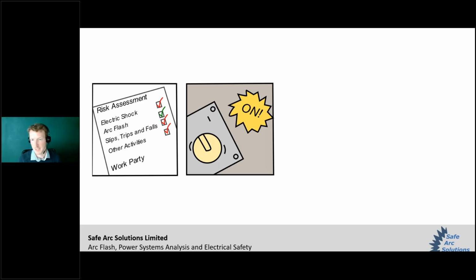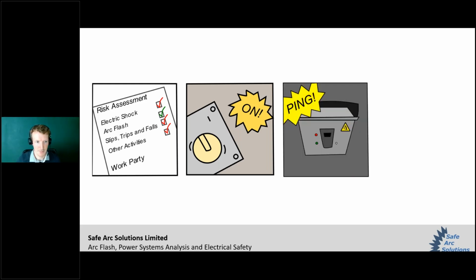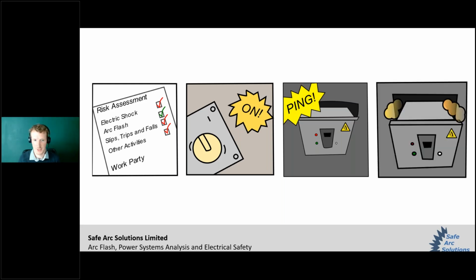So this time the task goes ahead, the breaker jams, but when it's shoved there's that same bright metallic ping, immediately followed by a brief flash of white light. But this time there's just maybe a lick of flames and a puff of smoke, and almost simultaneously the entire switchboard trips. Scott, who was pushing the breaker in at the time, steps back and looks a little stunned.